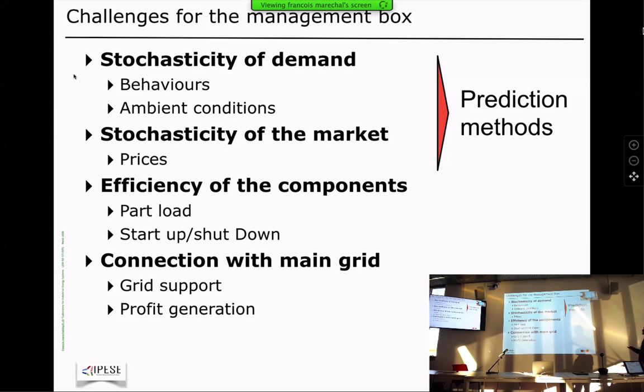Not only do you have to take into account the demand, the way people will behave, and the way your environment will evolve, you will also have stochasticity coming from the market. You also have to take into account the real technology: what is the real part-load efficiency of the equipment, how much time it takes to start up, what the energy consumption is for startup and shutdown, how long it has to wait before it can be restarted, and how it will connect to the grid.